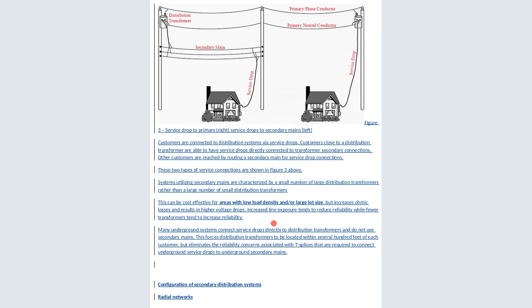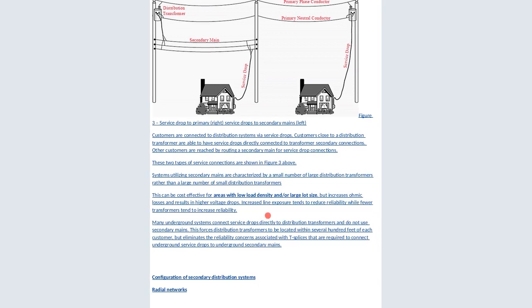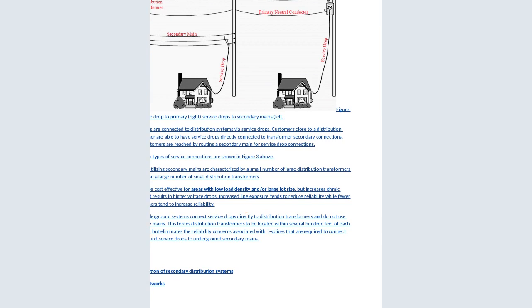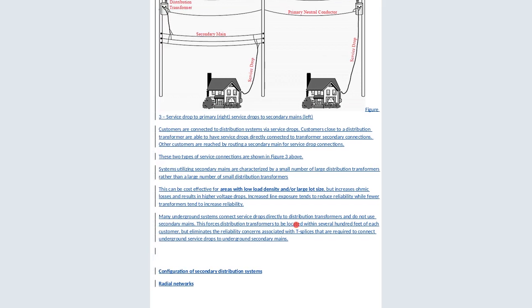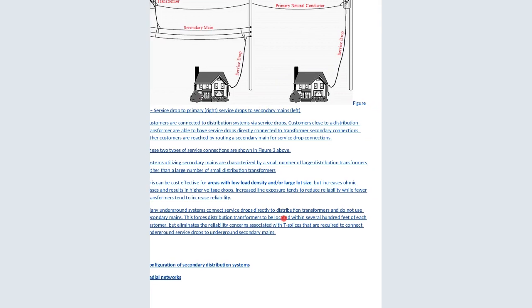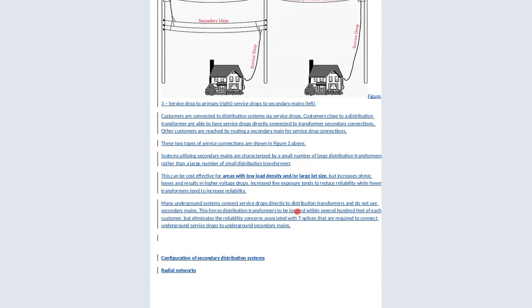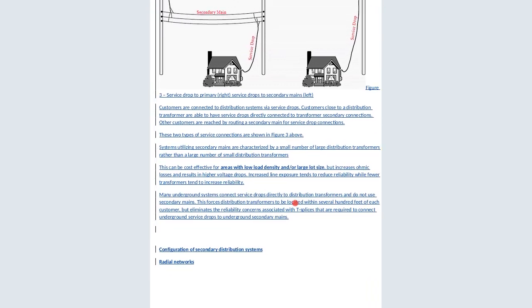And now the customers are connected to distribution systems via the service drops. You can see the service drop, normally called in the field the service cable. Customers close to the distribution transformers are able to have service drops directly connected to transformer secondary connections. Other customers are reached by routing a secondary main for service drop connections. The two types of service connections are shown in the figure.